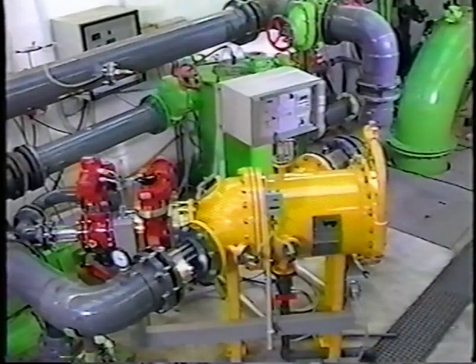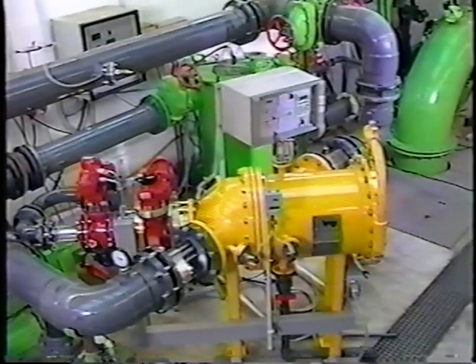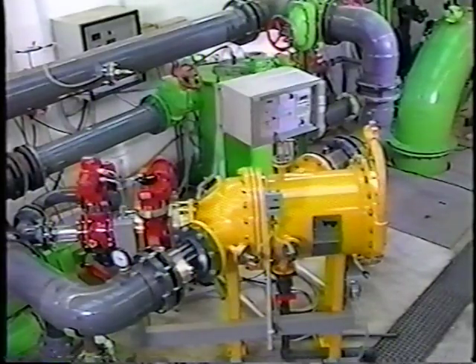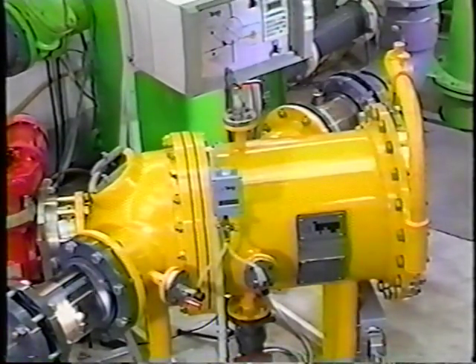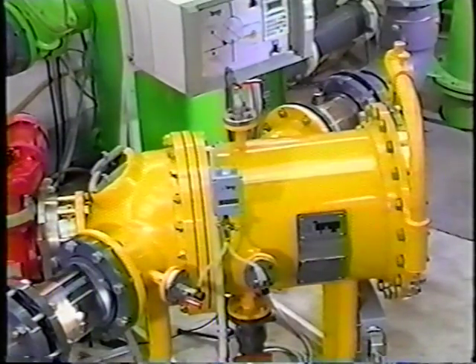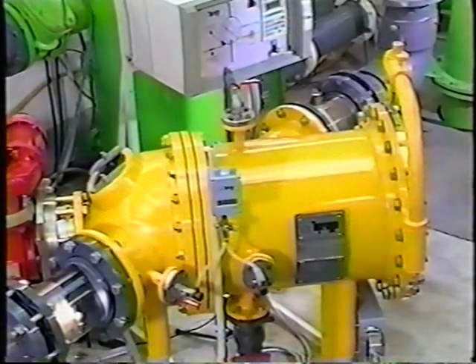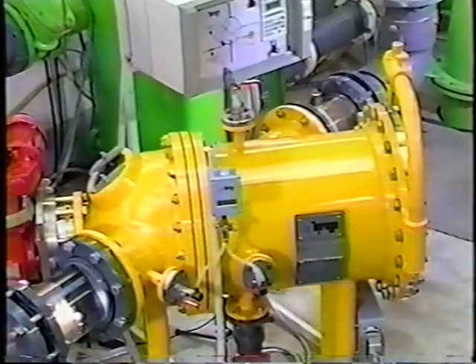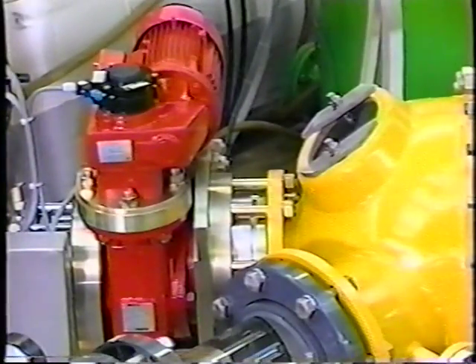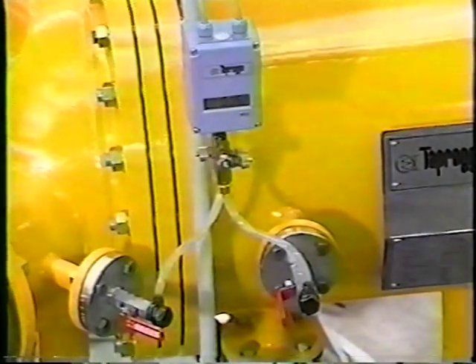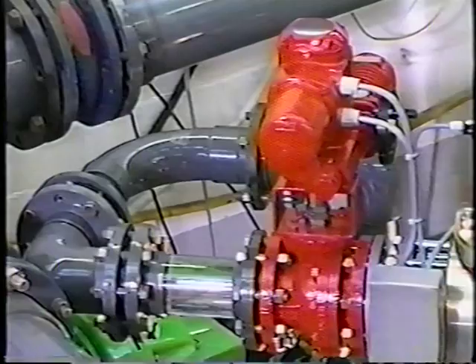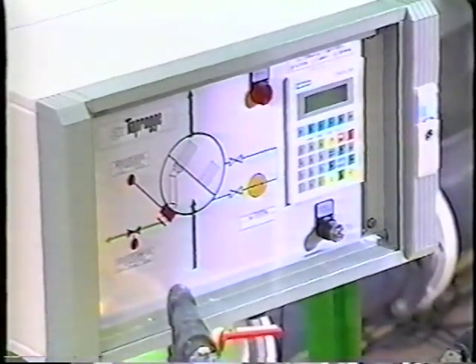Combining these filter cartridges with tried and trusted Taprogge technology produced the Pr-Bw 100FC. The Pr-Bw 100FC fine filter consists of a hemispherical inlet housing with an outlet housing which can be either hemispherical or, as in this case, cylindrical, the partition plate with sliding segment, the backwash rotor with sprung flushing shoe, the geared motor with bearing, the differential pressure measurement system, the backwash valve with positioning drive, and the control panel.